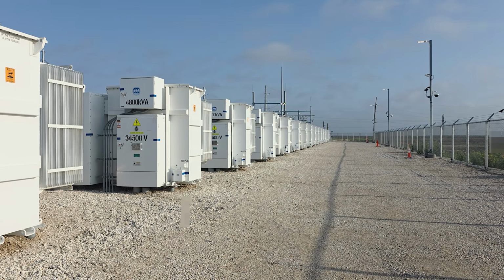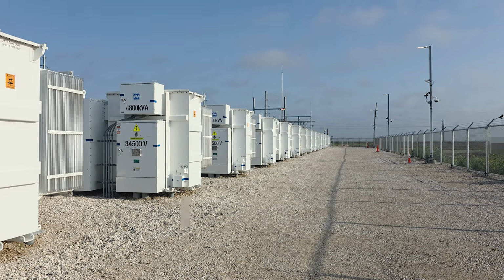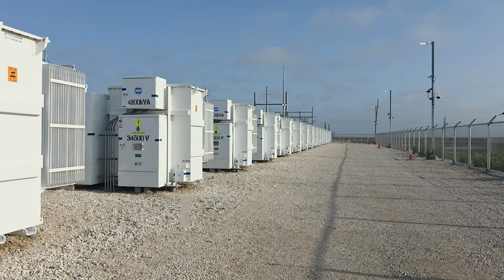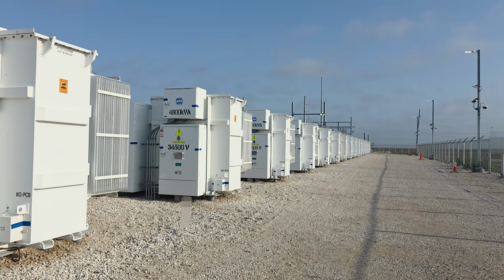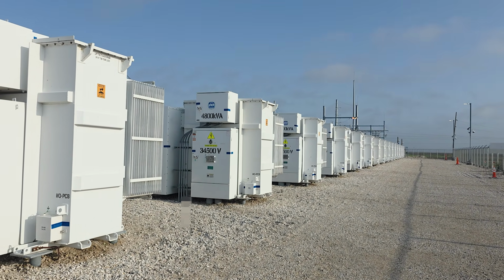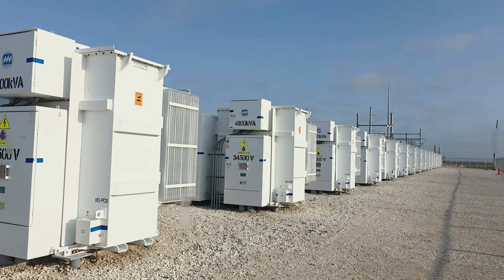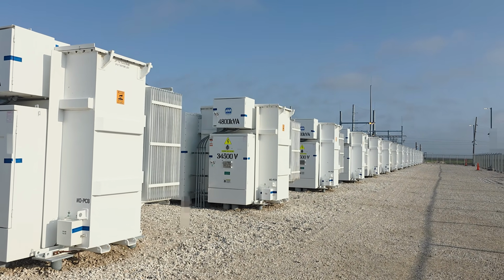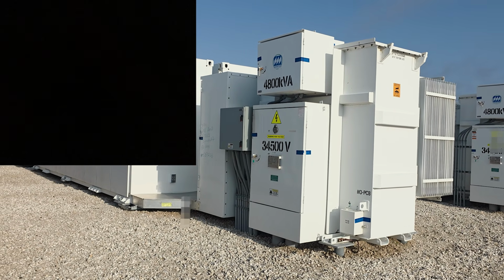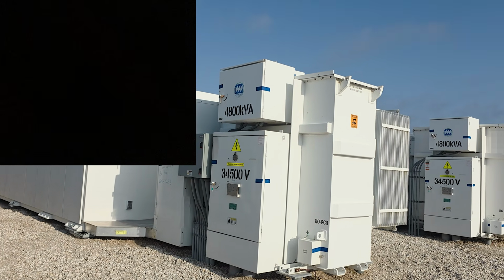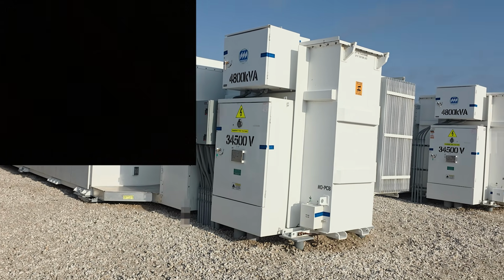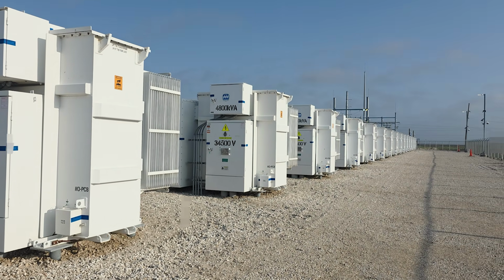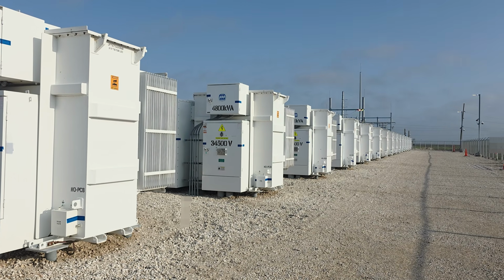These are getting pretty big. A 20 megawatt plant used to be considered pretty large. Now they're 300, 400, and 500 megawatt hour sites. This one's a 50. So they're getting big, but it's really a repeat of the same thing. The only thing that changes would be the size of the substation and the amount of feeders. That's about it. A lot of electronics in these things. I don't even know all of the capabilities. But again, they've got sensors in the transformers, sensors in the batteries. Everything talks to each other. And this is probably the substation and battery yard with the most advanced technology I've seen.